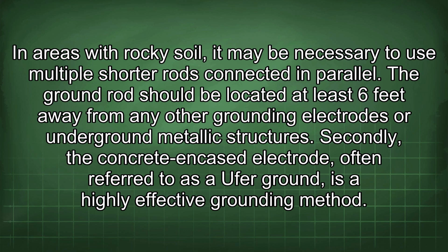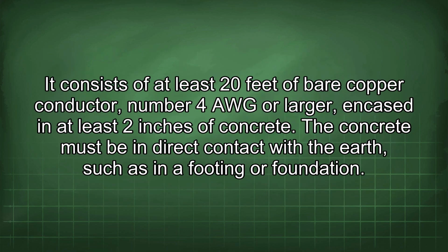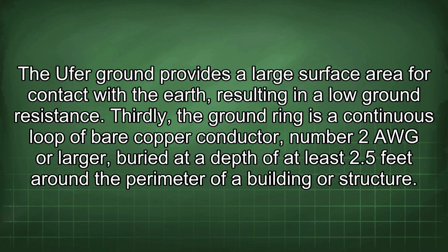Secondly, the concrete-encased electrode, often referred to as a Ufer ground, is a highly effective grounding method. It consists of at least 20 feet of bare copper conductor, number 4 AWG or larger, encased in at least 2 inches of concrete. The concrete must be in direct contact with the earth, such as in a footing or foundation. The Ufer ground provides a large surface area for contact with the earth, resulting in a low ground resistance.